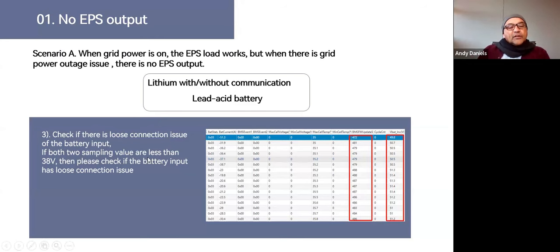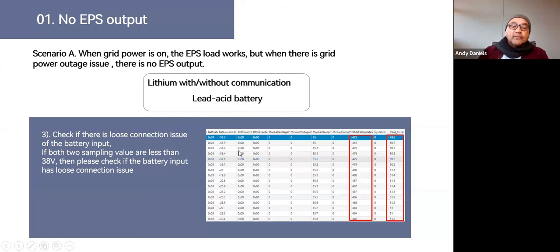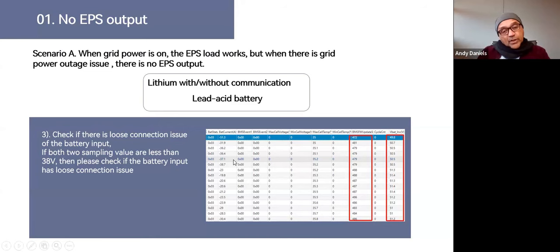Check that the two sampling values are the same. On the data history page, go to the BMS firmware column where BMS voltage is represented without decimals — so 472 means 47.2 volts, and 481 means 48.1 volts. You can also check the VBAT INV column on the far left against the other column. If the sampling voltage values are less than 38 volts, check the battery input cables and also use your multimeter to verify you're getting voltage on the battery output.